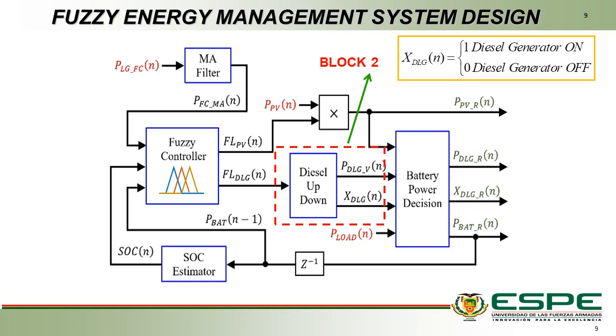Block 2 performs a state change at diesel generator startup and shutdown by considering minimum startup and shutdown times, to reduce fossil fuel consumption and try to get closer to an actual operation. This way, when the control strategy requires power from the diesel generator, the energy management system must turn on the diesel generator for at least 2 straight hours, then keep it off for at least 2 hours. Consequently, it reduces the cost generated by each generator startup and avoids a startup immediately after it is turned off, or vice versa.